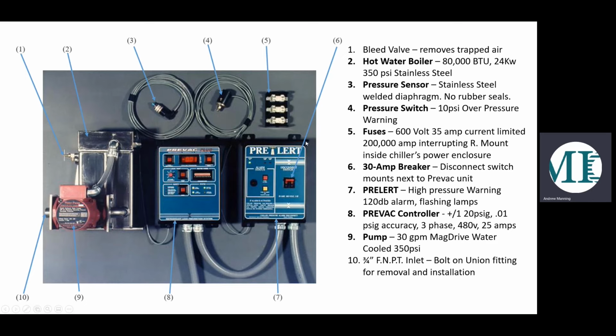Here's our PRELERT controller. This is where the power is going to come in. We've got the 30 amp breaker disconnect and the audible alarm for overpressurization with this pressure switch, which we'll get into a little bit later. Here's the PREVAC controller. This is where your readouts are going to be. This is where you perform the pressure seal mode and the leak tests.